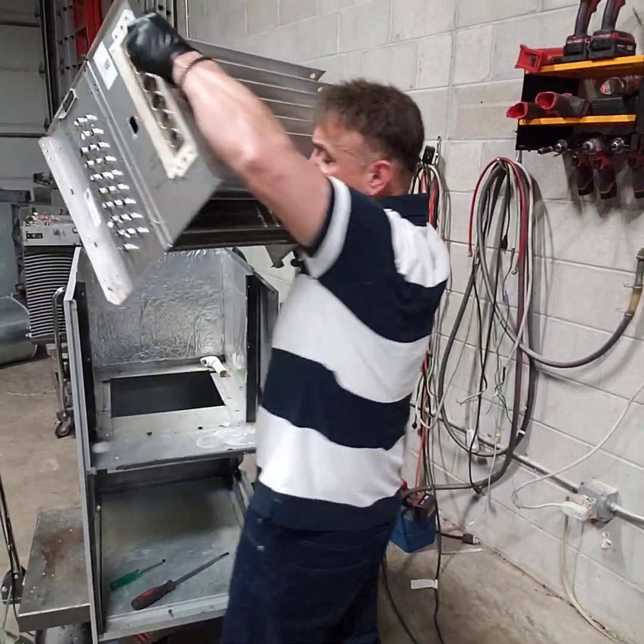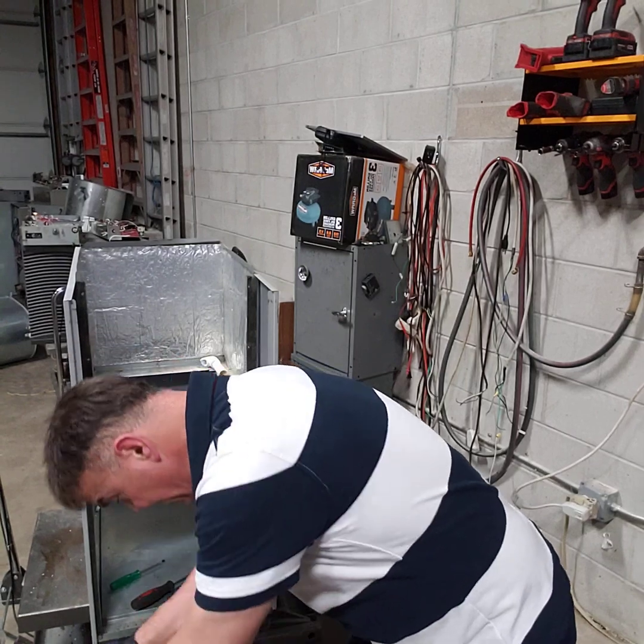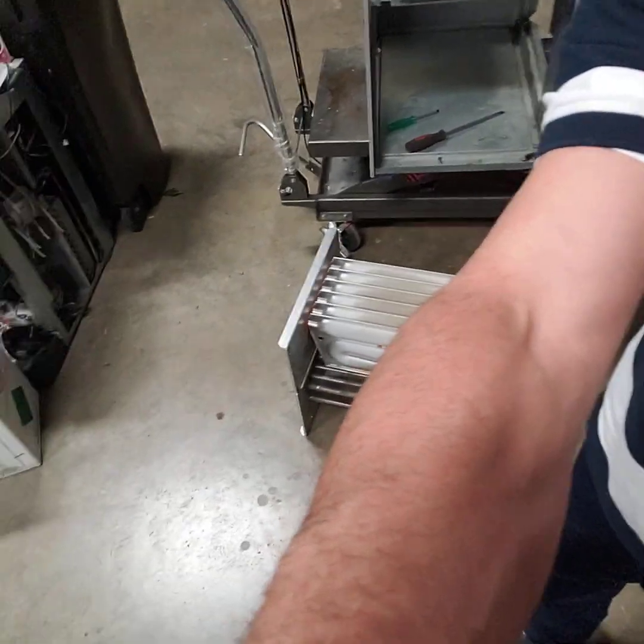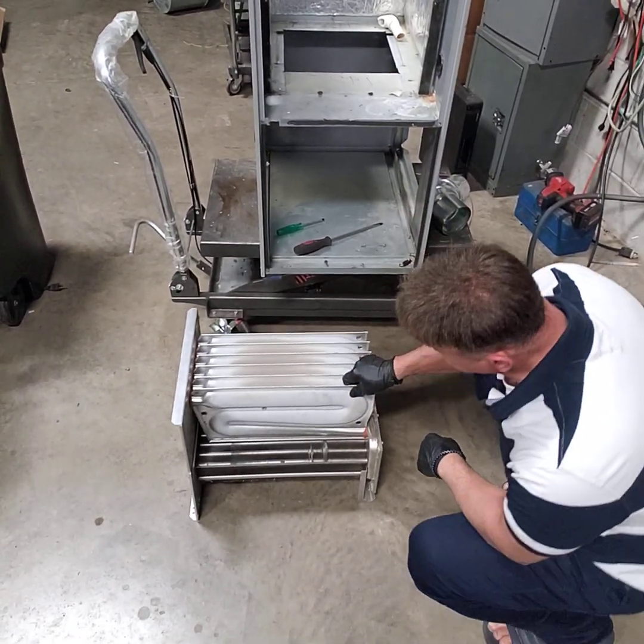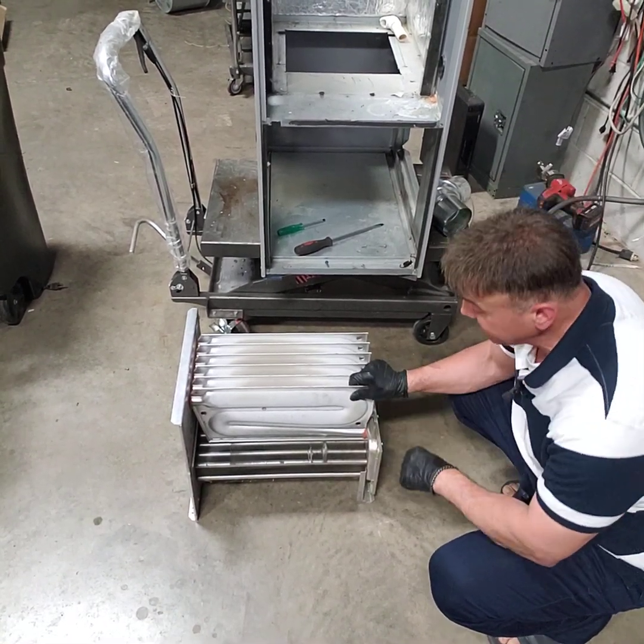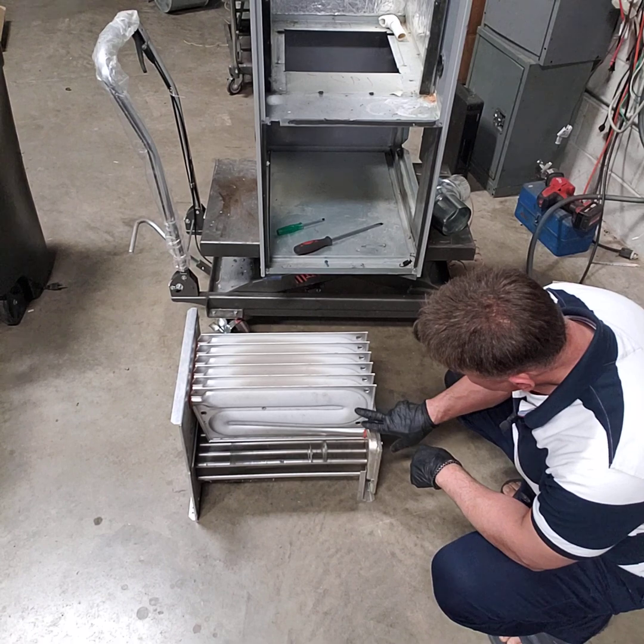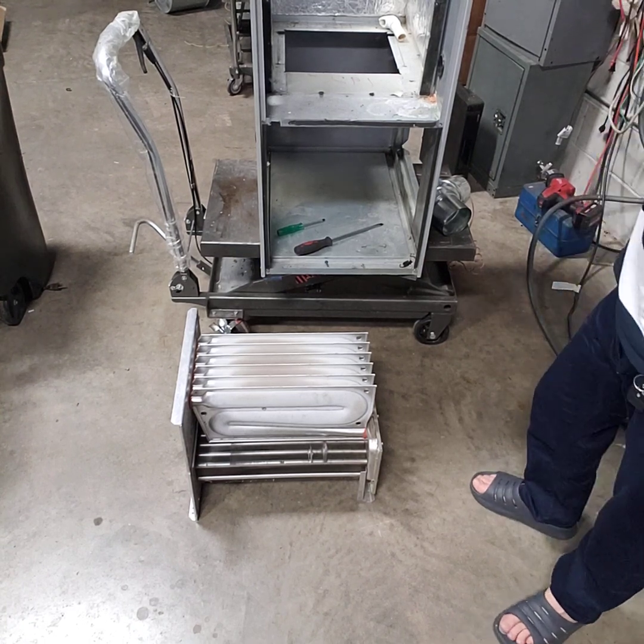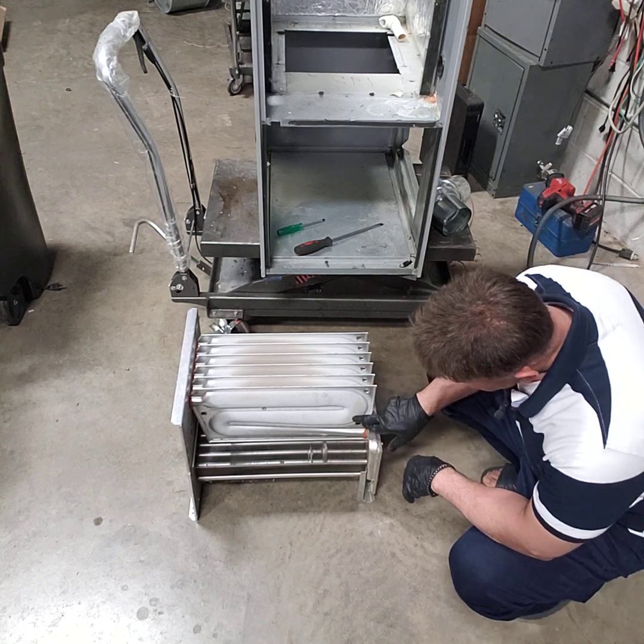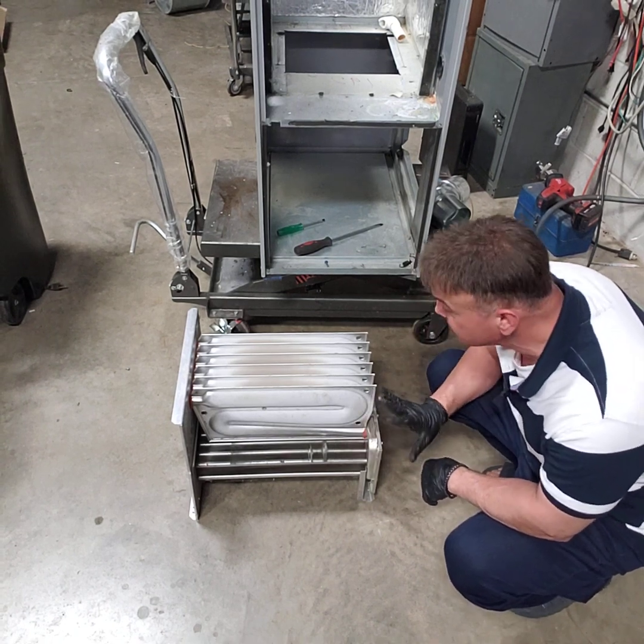What I'm trying to say about the, see this one here. If you see the other videos that I did earlier for other heat exchangers, for other models, there was a mark in here that indicated the furnace was pushing a lot of gas and it was burning like crazy. And no matter how much air you have coming, it wasn't able to remove the heat perfectly, so it will make a mark. Actually, I have the one I last worked on. I wish I could show it to you. But anyway, in the other video you can see it. So that means this furnace was not really sending a lot of fire. See, there's no marks. So maybe it was cool, which is really good.